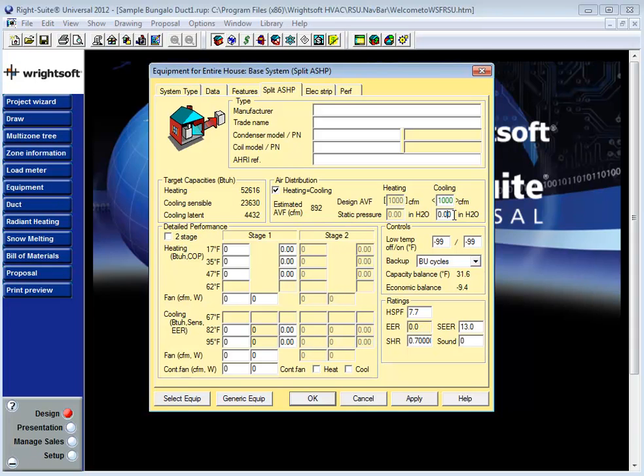At the end of the day it's these two numbers the CFM you'll be moving through your system and the static pressure conditions under which your fan can deliver that CFM that makes the equipment selection screen the first step of the duct design process.